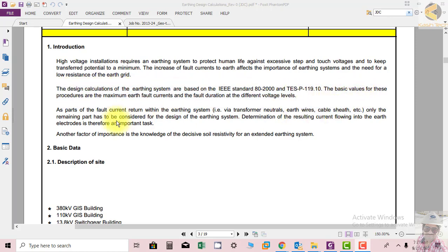The basic values for these procedures are the maximum earth fault current and fault duration at different voltage levels. As I told you, one of the most important calculations used to design a grid station earthing system is the maximum fault current. The other name of the maximum fault current is short circuit level, and it is for a fault duration at different voltage levels.